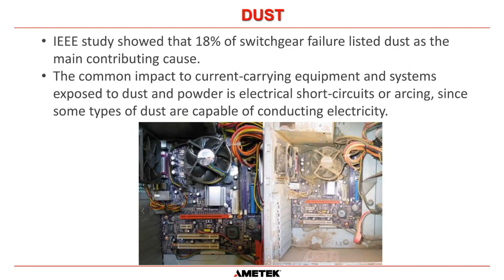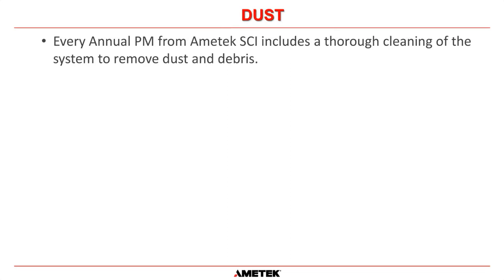rooms where you put equipment that aren't in such a clean environment, that you do regular cleaning of that system, okay? And every annual PM that AMETEK SCI performs includes a thorough cleaning of the system to remove dust and debris. It's extremely critical, because you've also got to remember that in most of our UPSs, there are large updraft fans pulling air through the bottom of the UPS system, up through the UPS, through the transformer, through the heat sinks on the top of the system, to get that air out of the UPS, to get that heat out of the UPS. And in doing so, if it is in a dusty environment, those fans are going to be drawing some dust into the UPS itself. It's inevitable, unfortunately.